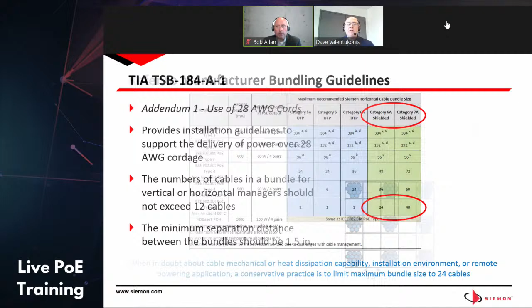And then there's also a TSB, another technical service bulletin, that talked about the use of 28 gauge cords, the smaller diameter patch cords that have come out in the last couple of years. The only problem is their findings were that to effectively do that, keep your bundle sizes to 12 and keep them 1.5 inches apart. I think that's a great engineering practice, but not a great practical practice. If you go into your horizontal and vertical management, it's really not practical to bundle those cables and keep them 1.5 inches apart. So at the very least, if you're doing 28 gauge cords in a PoE application, try to limit your bundle size to a group of 12. That's certainly going to help. And between some of the randomness in the pathways and maybe Velcro cable ties, you'll be able to achieve some level of dissipation there.